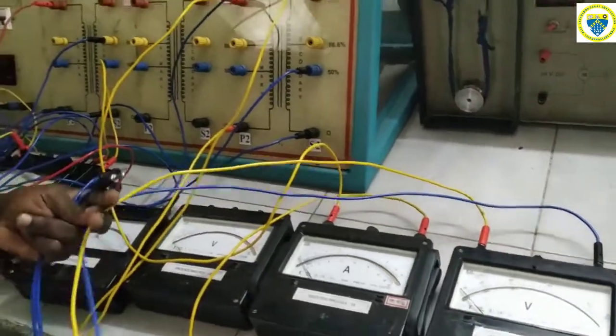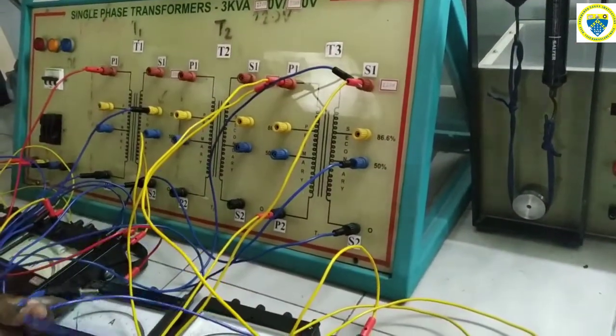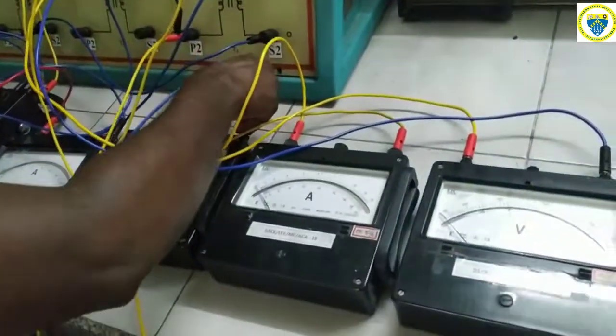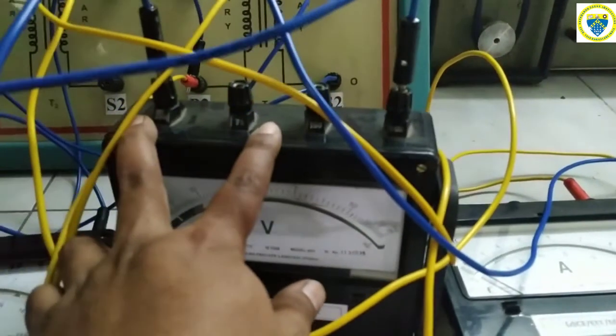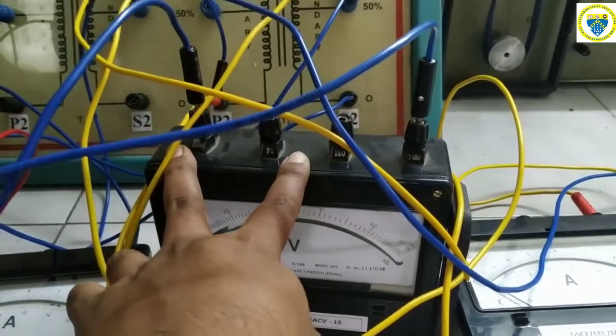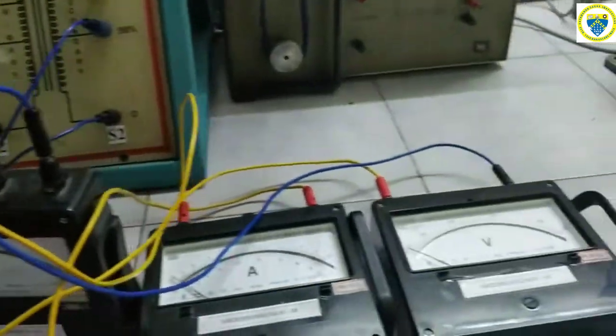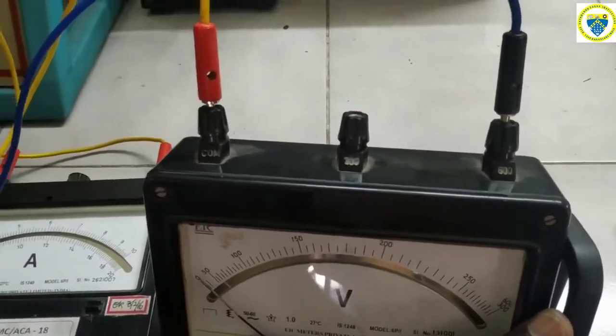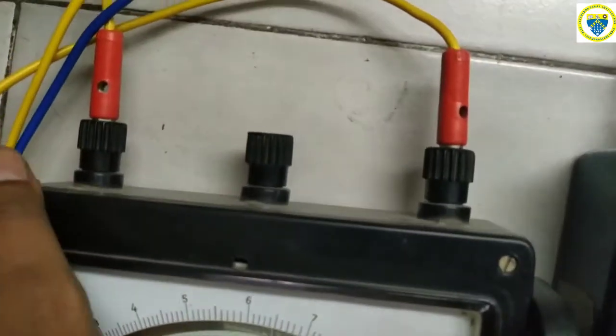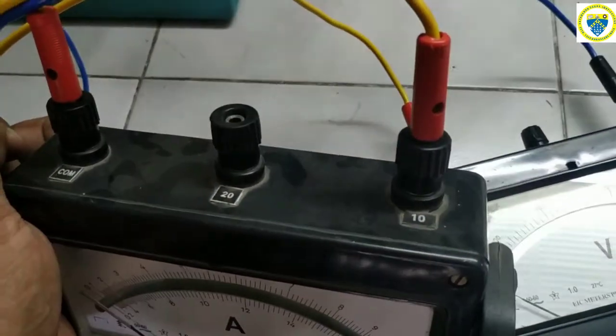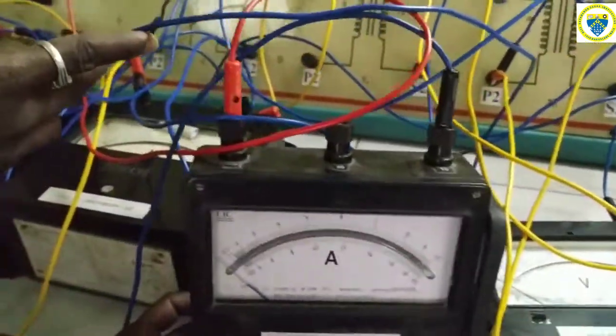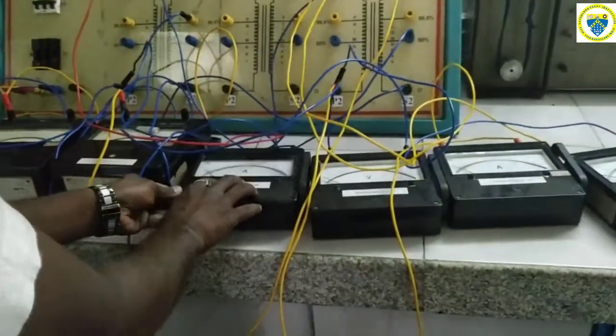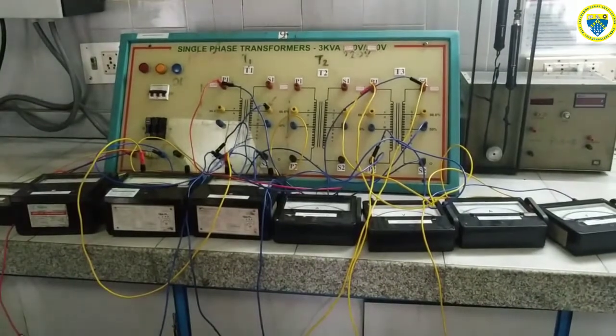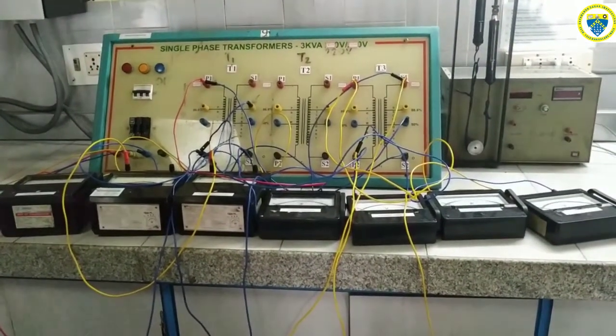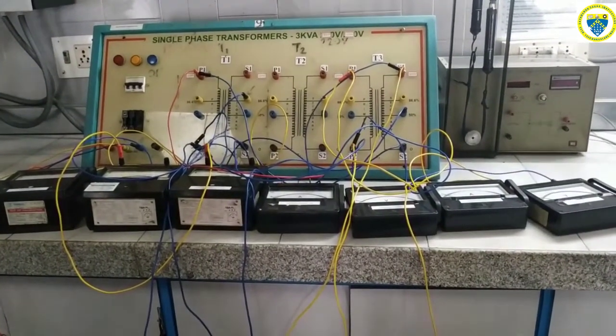One voltmeter should be connected to P1 P2 of the teaser transformer first, and then one more voltmeter of range 300, we are using a range from 0 to 300 volt. Anyhow we are converting from single to three phase, three phase to two phases, so 0 to 300 range is enough for both the voltmeters, and even the ammeter ranges are selected as 0 to 10 amperes. The 0 to 10 amperes range we will select for both the load side ammeters. This is the overall connection we make to have a SCOTT connected transformer for conversion from 3 phase to 2 phases. Let's see how exactly the conduction goes.